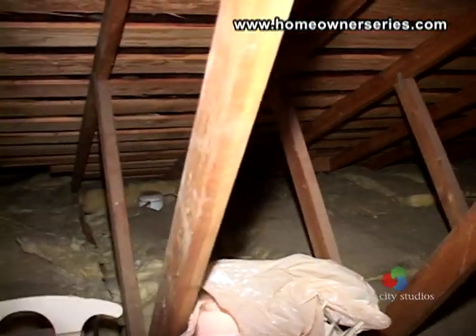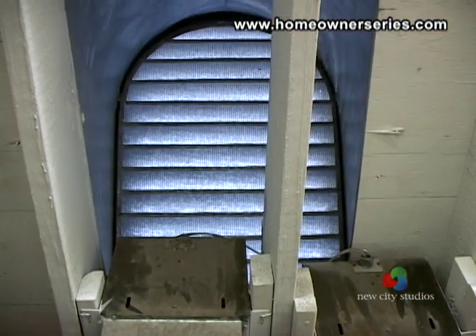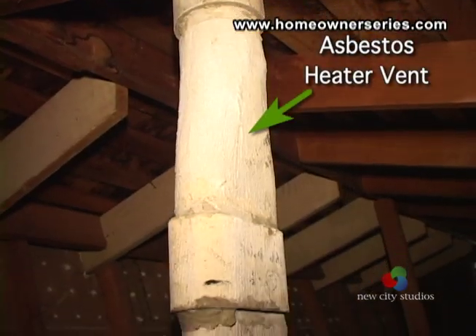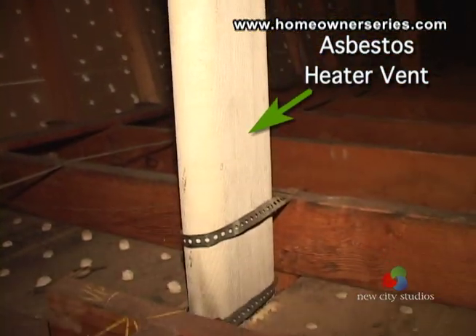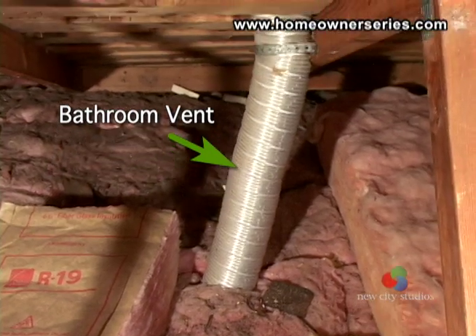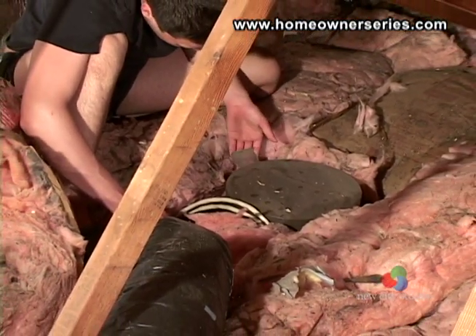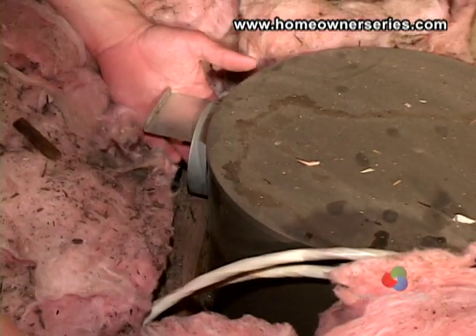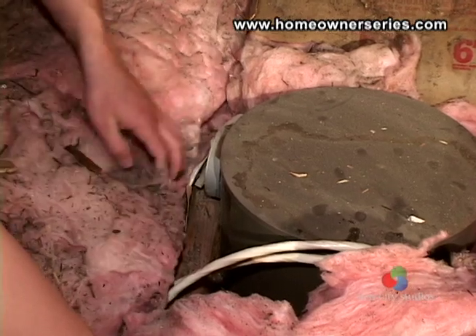Insulation and proper attic ventilation will minimize moisture concerns, like mold from condensation, by maintaining a more constant temperature in the attic. You should make sure air ducts and exhaust pipes from appliances, like the stovetop and bathrooms, are not broken and do not vent moisture, gas, or fumes into the attic. Nothing should vent into the attic itself. This bathroom vent blows moisture straight into the attic. Here you can see the long-term results of such improper installation.